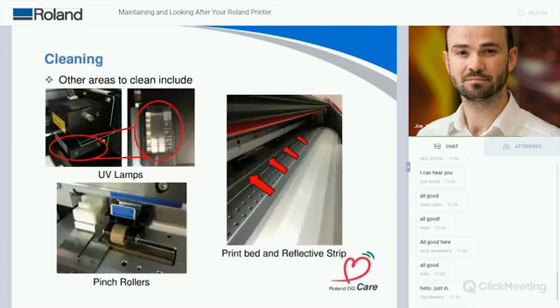So next up, just a few other areas you want to be cleaning. You have the UV lamp on our Versa UV machines. This is the underside. You'll be able to access this in manual cleaning mode, the same as you would with normal print head cleaning. The surface of the lamp is a little delicate, but if you clean it with isopropanol and a lint-free cloth, it should take any ink off the surface. What can happen sometimes is if any ink drifts and floats onto the surface of that lamp, it will cure solid. So periodically, give it a bit of a wipe down to keep it clear. Otherwise, you may find that the ink just doesn't cure very well on what you're trying to print onto.